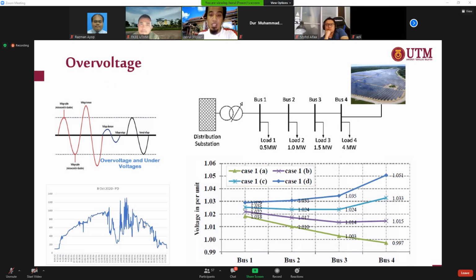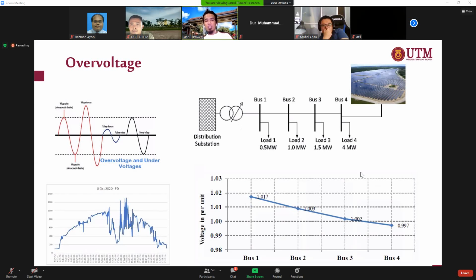That's the first case. The second, like I told you, since we cannot control our energy, isn't it? For example, in this pattern, we cannot control the energy. In other words, the voltage at bus 4, bus 3, bus 2, as well as bus 1. Bus 1 maybe is not really affected because it's very close to the substation. But for bus 2, bus 3, and bus 4, you can imagine that the voltage will fluctuate depending on the amount of energy being generated. So in terms of design, we need to make sure that, based on the worst case, meaning the largest energy that might be injected by the PV, the voltage will not exceed the over voltage limit. If not, you might have a problem. For example, let's say you use an auto tap transformer. Let's say initially the voltage here is very low, so you tap the transformer to improve the voltage.